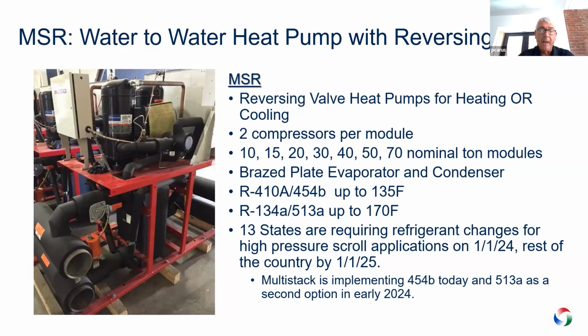We also do that same type of application using 134A. We will be adding 513A and be able to go up to 165 to 170 degrees Fahrenheit. That's going to be a little bit farther along in terms of its development. 513A is not as popular. 134A was not as popular in the scrolls. So we're going to be developing that starting in 2024, and by middle of 24, we should have both 454B and 513A available in this reversing valve heat pump solution.